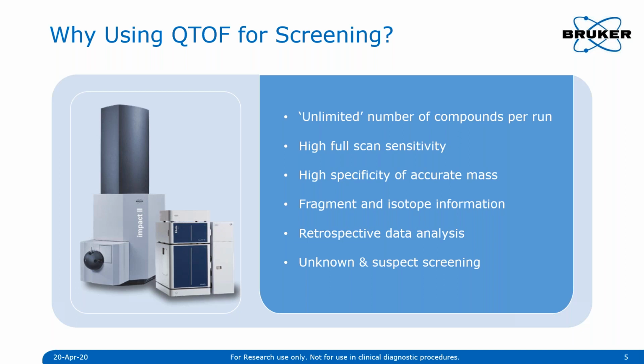Secondly, QTOF instruments can capture all the data all the time. And that means that data can be analyzed even retrospectively, either for specific compounds added to the database using standards, or for suspected compounds based just on their molecular formula. And lastly, QTOFs are high-resolution systems, and they're less susceptible to space charge effects than, say, ion traps. It means that they can utilize accurate mass and isotopic pattern measurements for confident identification of analytes and be less susceptible to interferences.